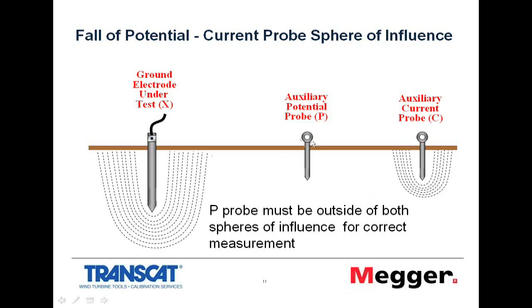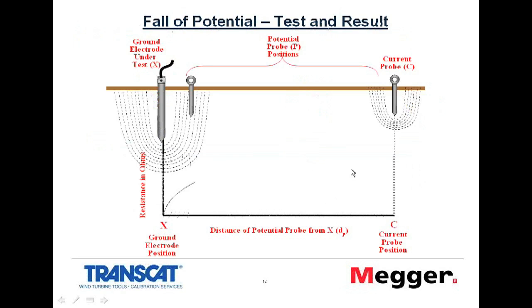How do I know whether this potential probe is outside the sphere of influence? Well, I have to do a number of measurements, placing the electrode at equal spacing between the two, the system and the current, and plot the graph. And this is what I would do.